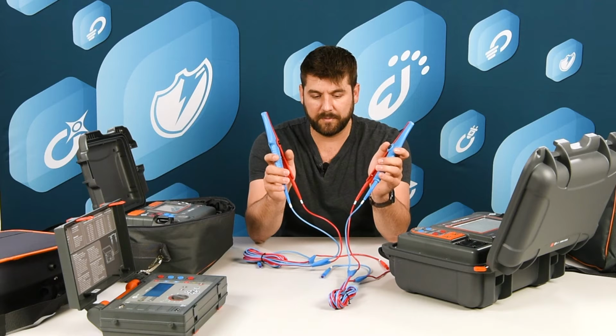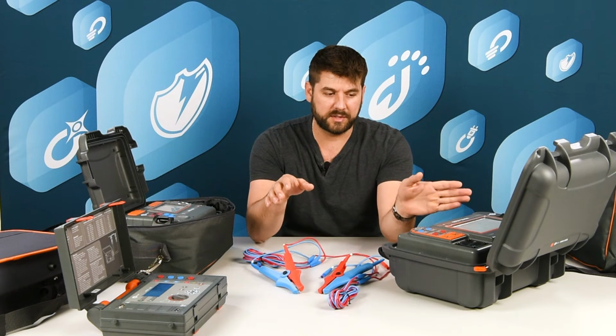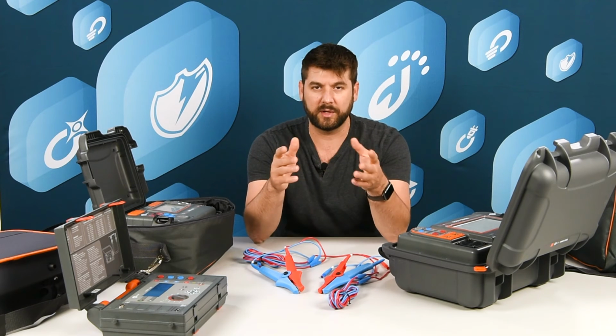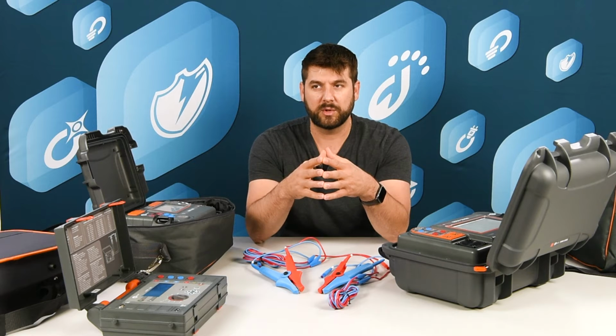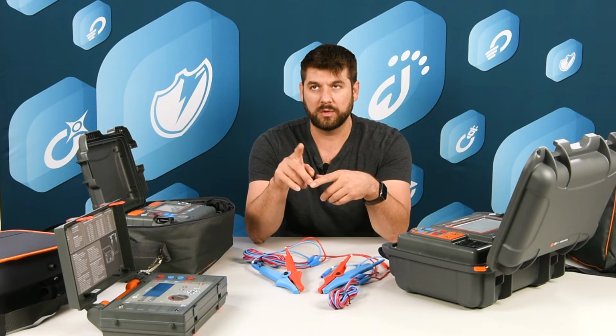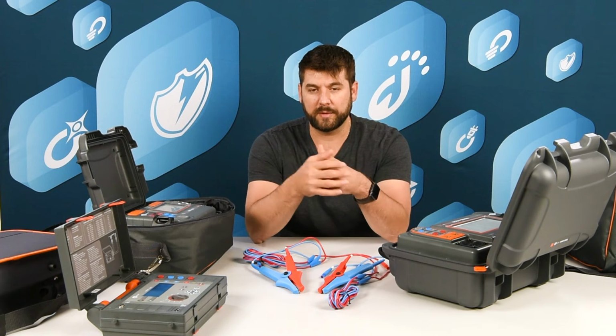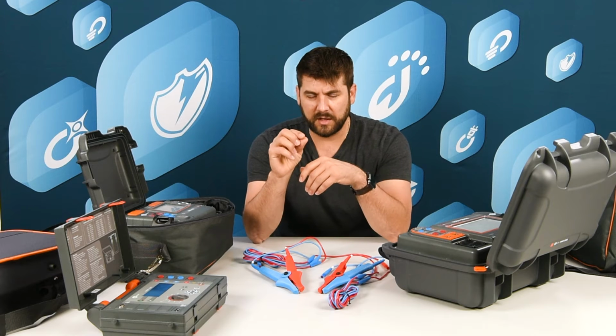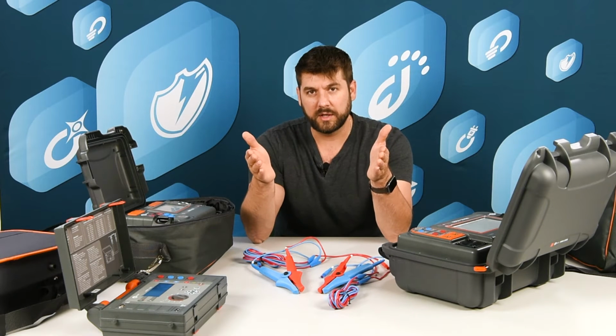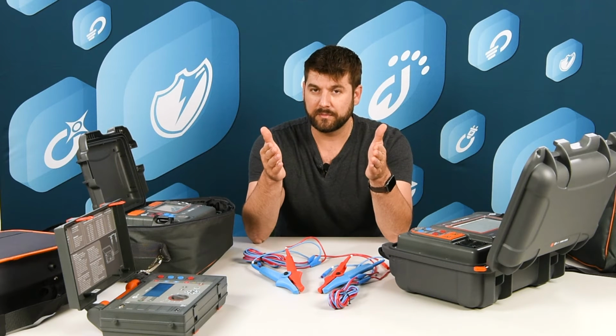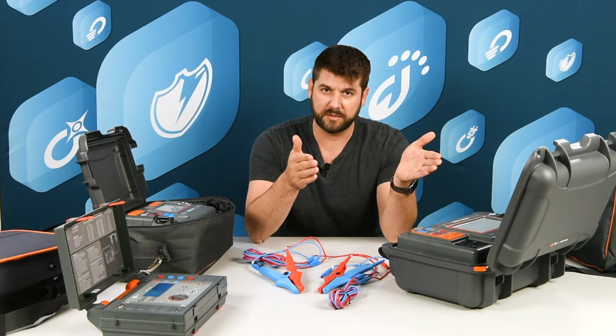So we measure the voltage drop. The instrument is telling us how much current it's put out. So there we have the current and we have the voltage. Calculate the resistance. Resistance would equal the voltage divided by the current. So if a given amount of current, if I have a lower voltage drop, I would have a lower resistance.